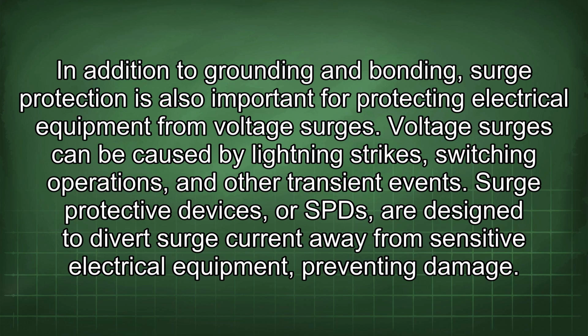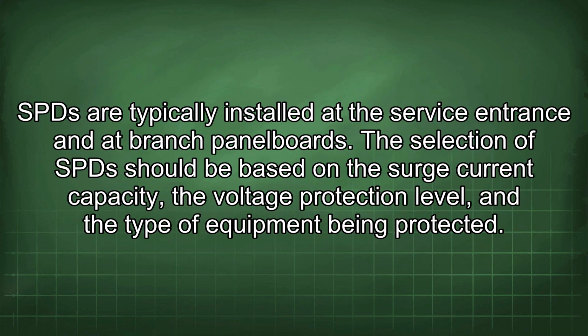In addition to grounding and bonding, surge protection is also important for protecting electrical equipment from voltage surges. Voltage surges can be caused by lightning strikes, switching operations, and other transient events. Surge protective devices, or SPDs, are designed to divert surge current away from sensitive electrical equipment, preventing damage. SPDs are typically installed at the service entrance and the branch panel boards. The selection of SPDs should be based on the surge current capacity, the voltage protection level, and the type of equipment being protected.